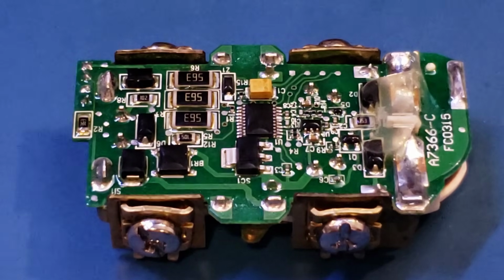There are a lot of other safety features in these modern GFCI receptacles. One such feature, for example, is that they're usually shipped in a disconnected state. And once you wire it up, it will detect whether the wiring is correct or not before you can actually reset the device, and that's an additional safety feature. So that's all I wanted to cover in this video. Hopefully now you know the effort that goes into the designs of these GFCI receptacles, and I'm still amazed at how many patents are out there just for a single device like this.